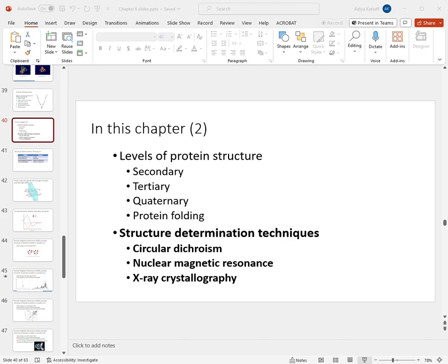When you have a protein that has mostly alpha helix character and you measure a CD, you will see minima around 208 nanometers, and then again around 220 for an alpha helix. That's different than if it looks like a beta sheet. For a beta sheet, we'll actually just see more of the singular minimum right around 215 nanometers. And that's very different from a random coil, where we'd see this minimum right around 198 nanometers.